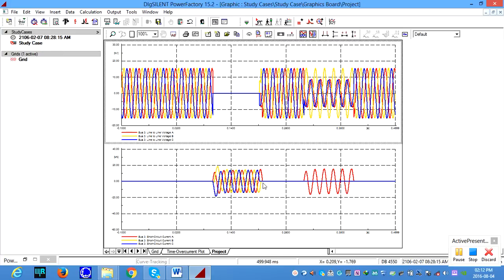Then after 0.2 seconds the three-phase fault is cleared and the system is building up the voltage back to 11 kV. After 0.3 seconds we introduce a single line to ground fault on phase A. It means the phase A voltage collapses and you can see the phase A current builds up. At 0.4 seconds we clear the single line to ground fault and the system tries to build up the three-phase voltage again. So that is the concept.